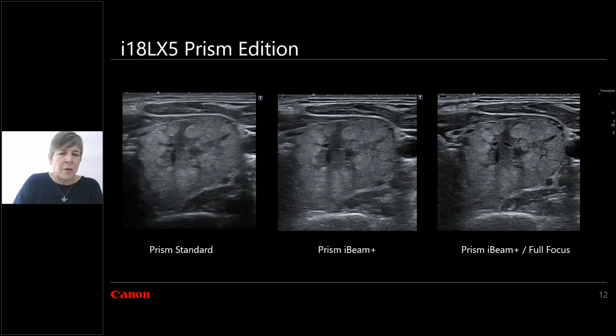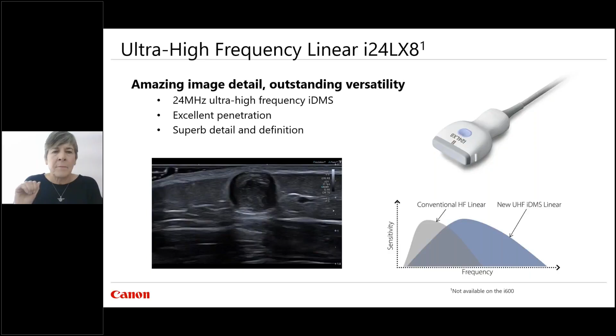We also utilize a 24 megahertz transducer quite a bit for breast imaging. When Canon first came out with this transducer, I was like, okay, great, what are we going to do? Scan the first centimeter? But it has really excellent penetration and resolution at 24 megahertz. And now with the iBeam Plus, we have even better penetration for that.